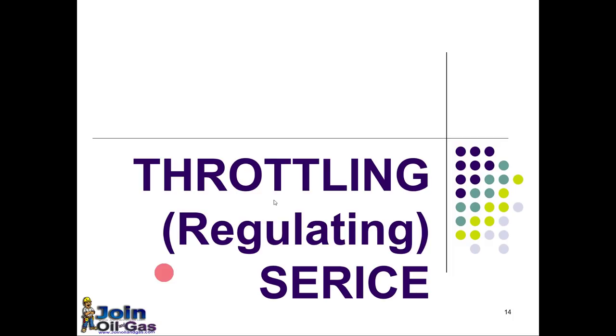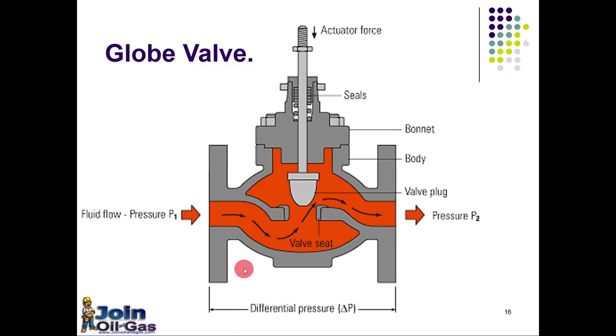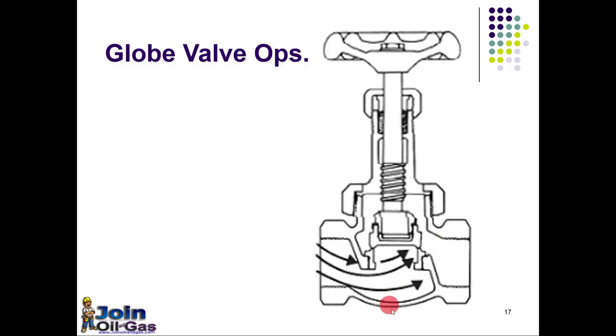Now let's see the throttling or regulating service valves. For this service we mostly use a globe valve. A globe valve is shown here with various parts: valve seat, body, bonnet, stem seal, and a valve disc. By lifting or lowering the stem, it will increase or decrease the opening — this is how the flow is controlled or regulated. When the disc is open there is flow, and when it is lowered the valve is closed and there is no flow.